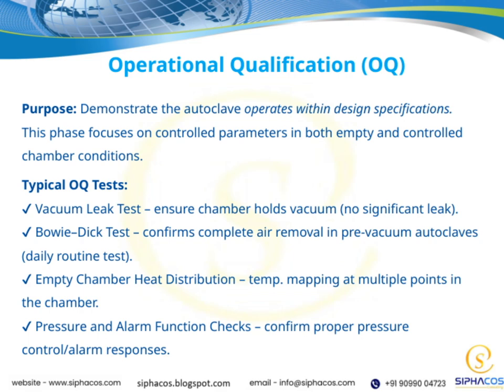We also conduct an empty chamber heat distribution test. This involves temperature mapping at various points inside the chamber to make sure heat is evenly distributed, a key factor for effective sterilization. Lastly, we check the pressure and alarm functions. This step confirms that the pressure controls are working correctly and that alarms will activate properly if any parameters go outside of safe limits. All these tests together help us verify that the autoclave is operating reliably and safely, which is fundamental to maintaining high standards in our sterilization processes and overall quality assurance.